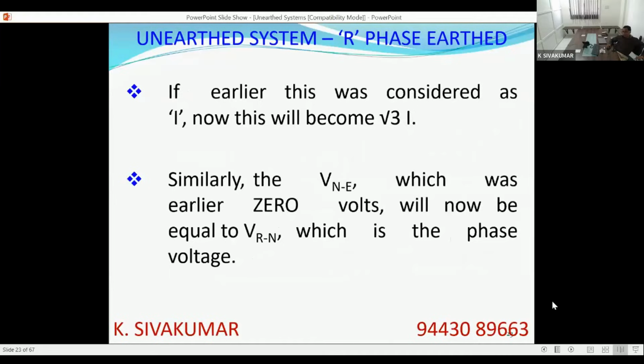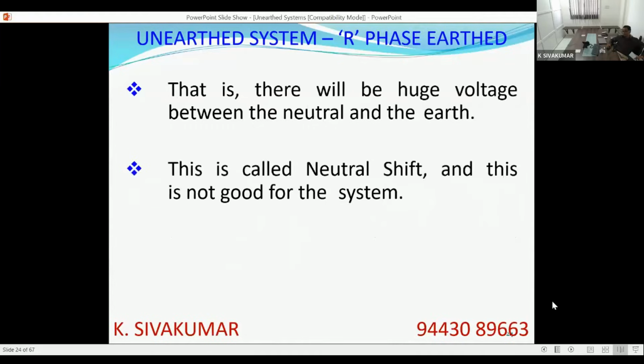Also, earlier neutral and earth were at the same potential, so there was 0 volt between neutral and earth. But earth is now R phase. So the neutral and earth voltage will be the neutral and R voltage. So neutral will show phase voltage now, because earth is R phase now, and the voltage between neutral and earth will be the voltage between R and neutral, that is phase voltage. So the neutral will shift itself. There will be a huge voltage difference between neutral and earth. Neutral will shift from its 0 voltage to equal to phase voltage now. And this will create its own set of problems.